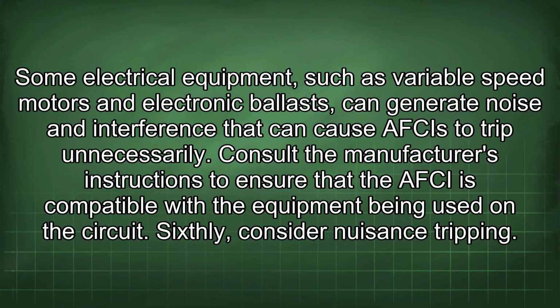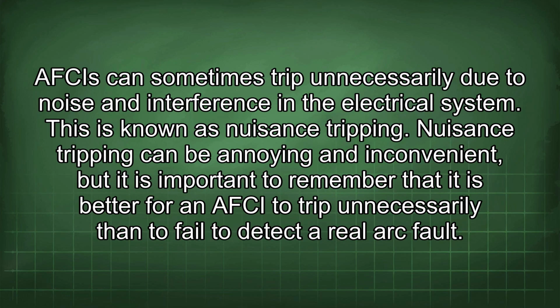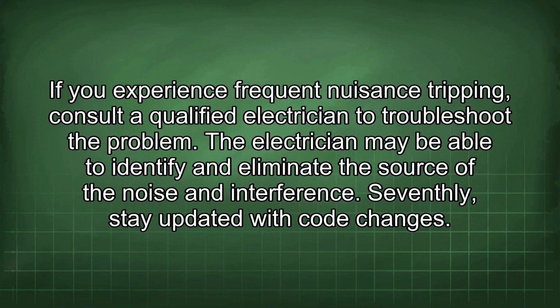Consult the manufacturer's instructions to ensure that the AFCI is compatible with the equipment being used in the circuit. Sixthly, consider nuisance tripping. AFCIs can sometimes trip unnecessarily due to noise and interference in the electrical system. This is known as nuisance tripping. Nuisance tripping can be annoying and inconvenient, but it is important to remember that it is better for an AFCI to trip unnecessarily than to fail to detect a real arc fault. If you experience frequent nuisance tripping, consult a qualified electrician to troubleshoot the problem. The electrician may be able to identify and eliminate the source of the noise and interference.